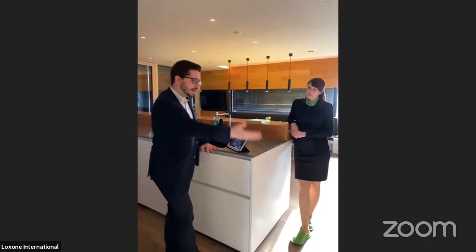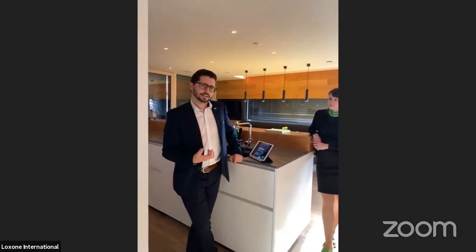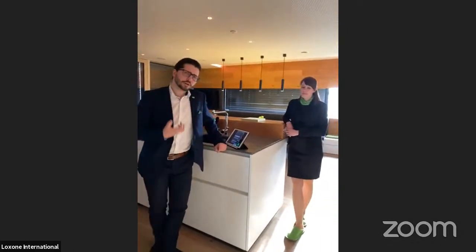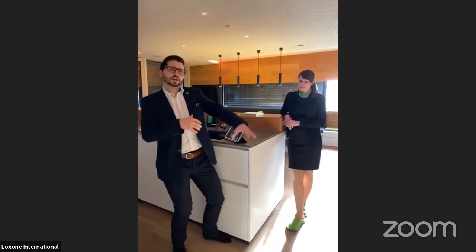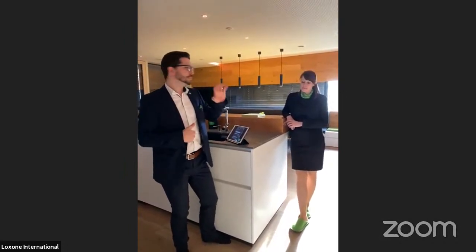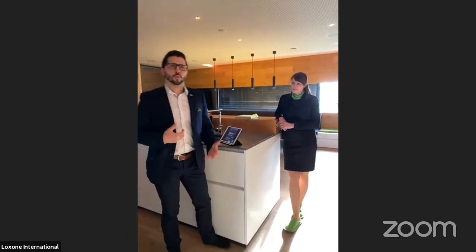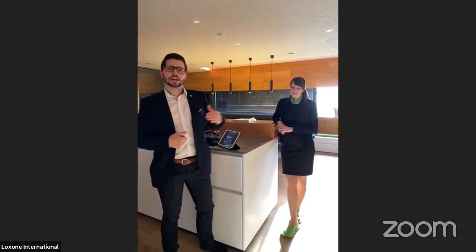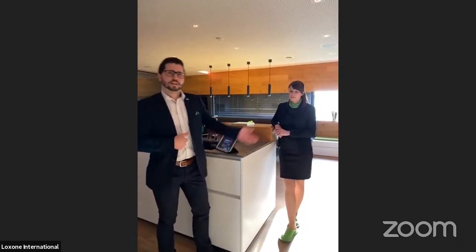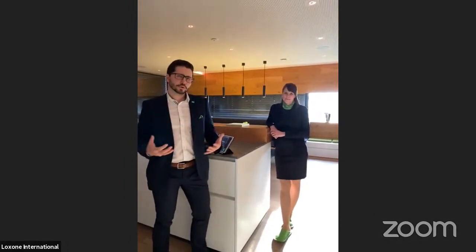And nobody knows, right? Because it depends if you have radiators or underfloor heating or air conditioning or HVAC or whatever, it depends. So our system learns the room's behavior. When you install Loxone the first day, it will start soon ahead, a couple of hours, and then it will start heating. And then it knows, okay, it was way too soon to start, because I want to have temperature at 6, but I reached it at 4. So the next day, it will start later. So it learns exactly how long it takes to heat up the room.